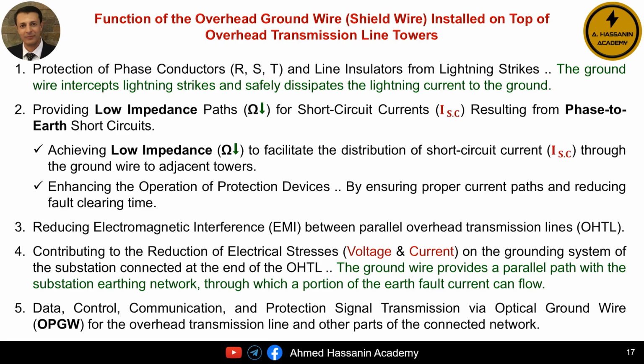The fifth function of the shield wire or earth wire or ground wire, as I mentioned earlier, is that if the earth wire is of the optical ground wire, OPGW type, it will be used for data transmission, control signals, communications, and protection related to the transmission line, as well as between different substations and control centers.